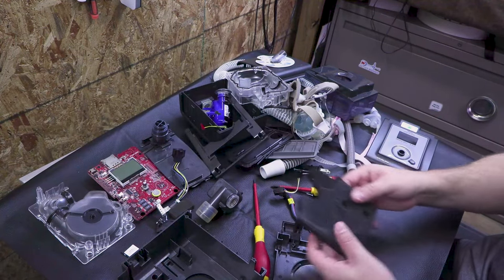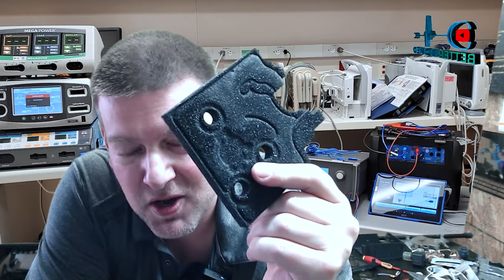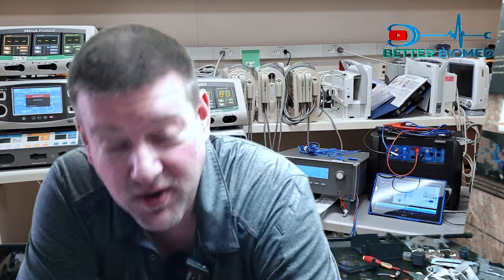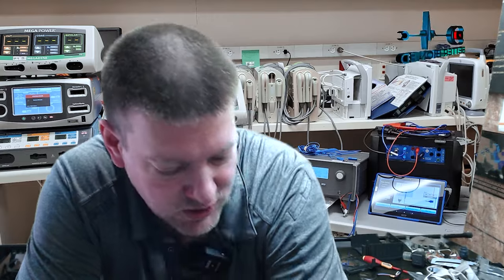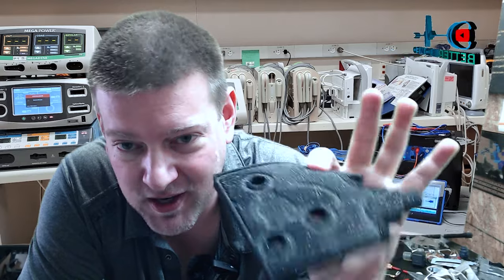That is the inside of a Philips CPAP, and here is the problematic foam. You can see the discoloration — it's already starting to break down. Whether or not this one was on the recall, it's definitely something to be cognizant of, because usually if you have one manufacturer of a common component like foam, you source it from one place for cost and quality control. Just a quick deep dive into the inner workings of a CPAP and humidifier. If you guys have one of these units, check online — there is an active recall on about 20 different CPAPs and BiPAPs. Look out for your friends and family as well. Thanks for watching.